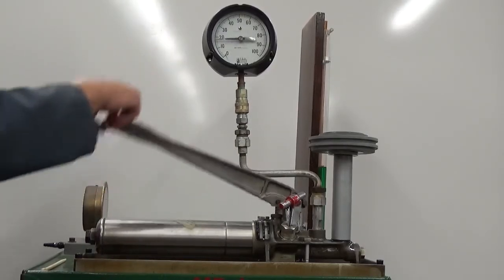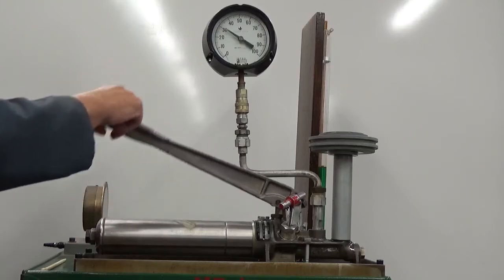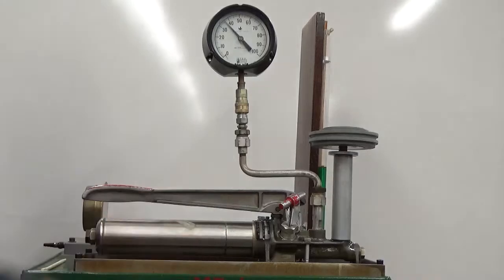Continue pumping until the piston lifts the dead weights off its seat. Once this has happened, we've reached the point where the calibration weights are exerting exactly 45 psi on the oil in the system. The pressure can now be read off the gauge and used in your calibration curve. This process can now be repeated for all the calibration points listed in the lab manual.